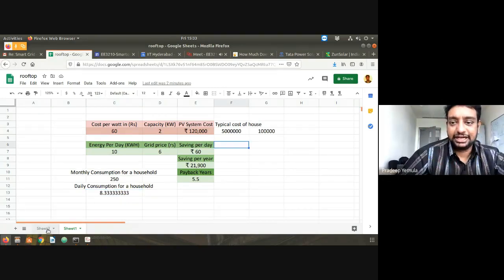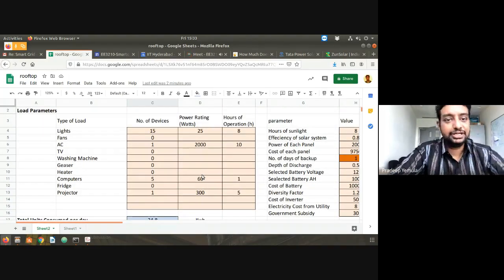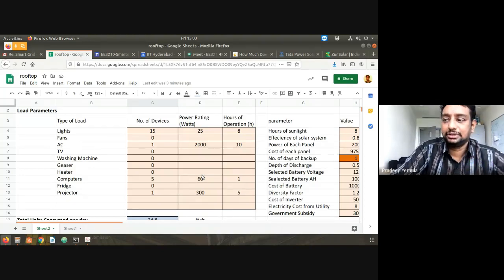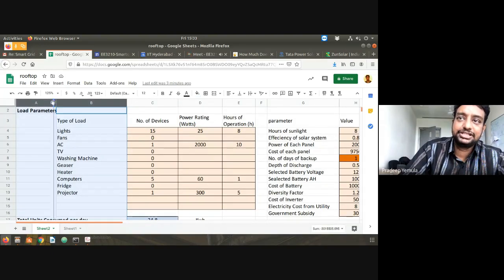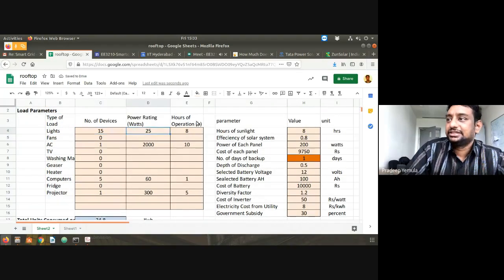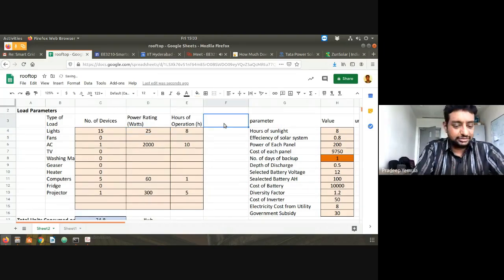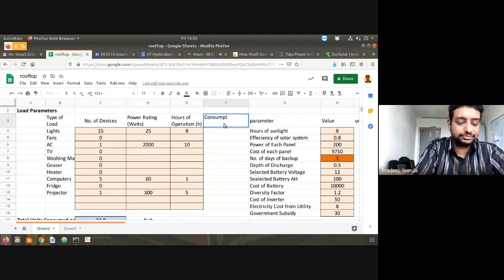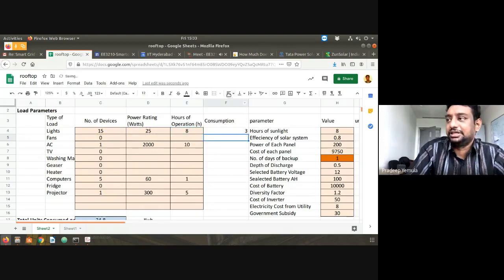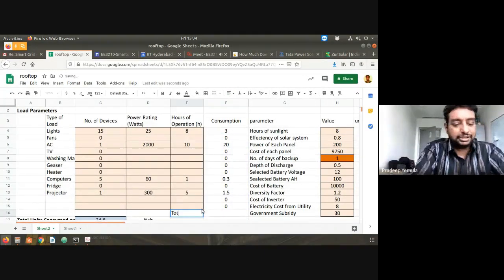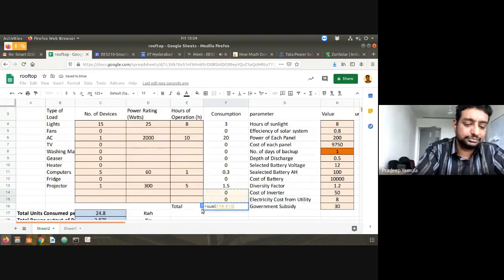Let's do a more detailed analysis. First, you have to do a load analysis — what is your load? I have prepared a simple Excel sheet. The consumption formula is: number of devices multiplied by power rating of the device multiplied by hours of operation, divided by 1000 to get consumption in kilowatt hours. Total consumption comes to about 24.8 units.